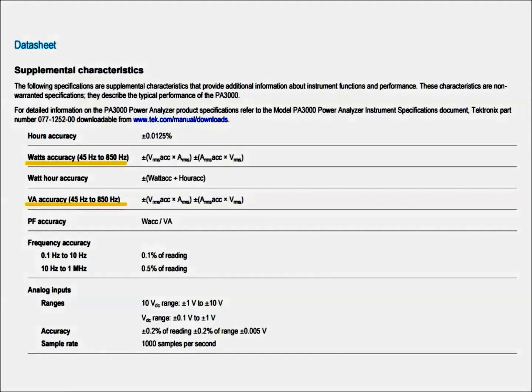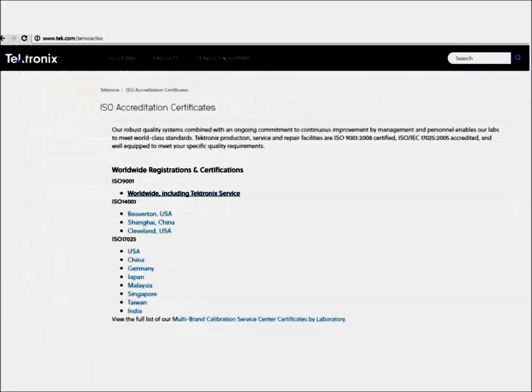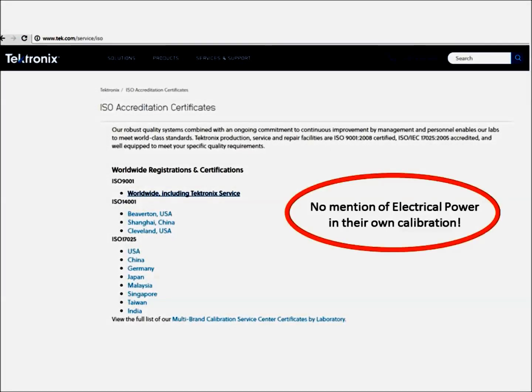Although not highlighted here on this screen, the first paragraph is also a strange one. As I understand, their power analyzer has a non-warranted specification for measuring power. Finally, their calibration has no mention of calibrating power anywhere. I've looked through each of the scopes of accreditation, and none of the calibration laboratories on this list have any mention of electrical power. It can mention RF power, but not electrical power.